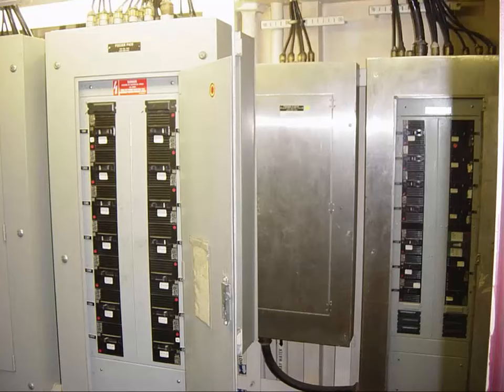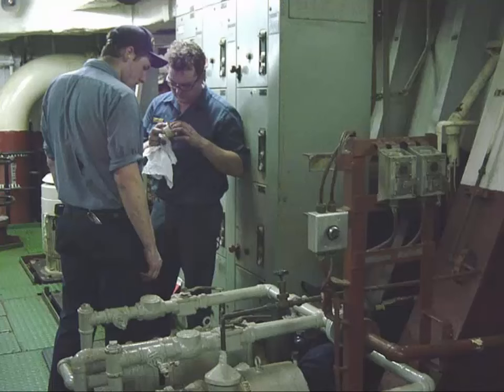But if you're talking of, say, a light in your room, it is first that power comes off the main board, goes to a circuit breaker protecting the transformer, and then you have a circuit breaker off the 115 volt distribution that is going to a power panel, and it has a circuit breaker to protect the cabling to that power panel. And then at the power panel, you have circuit breakers that protect each individual circuit.